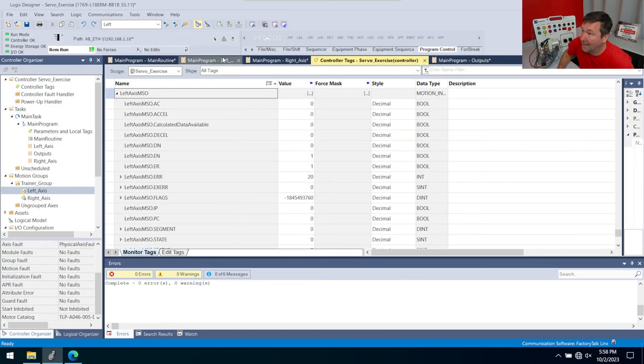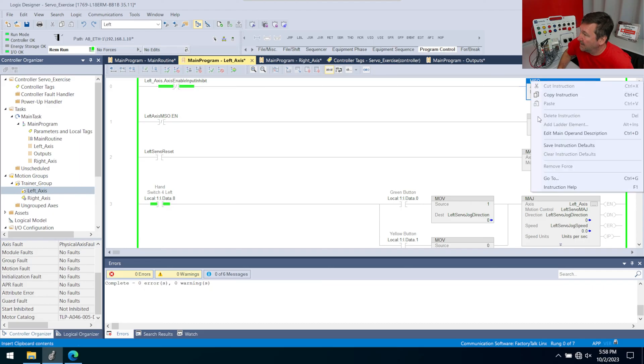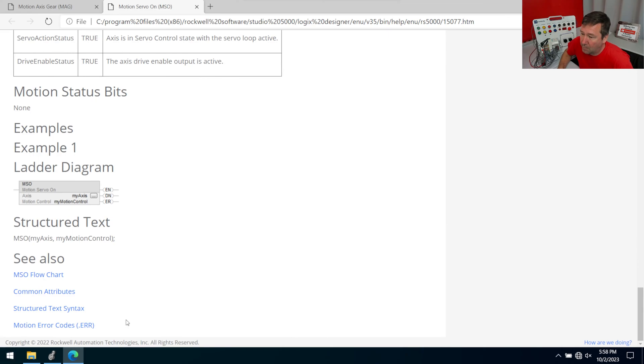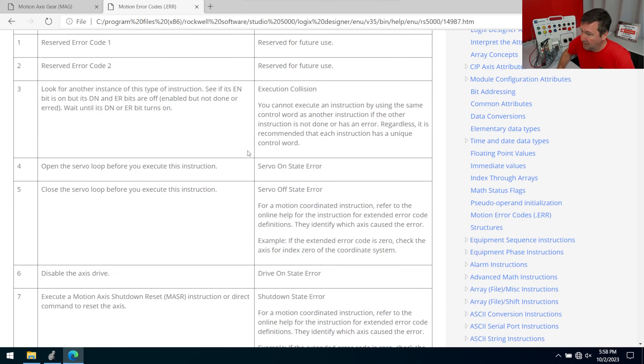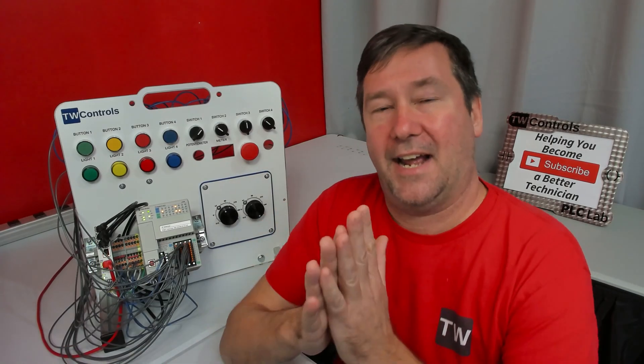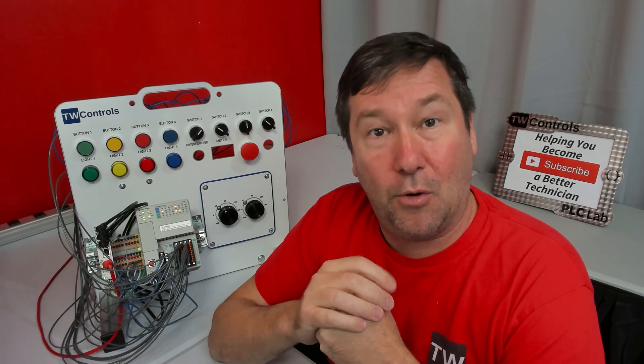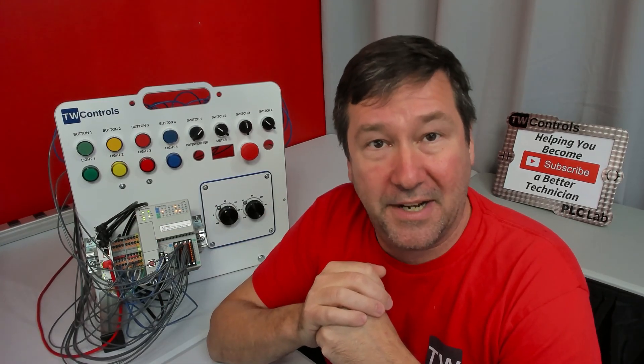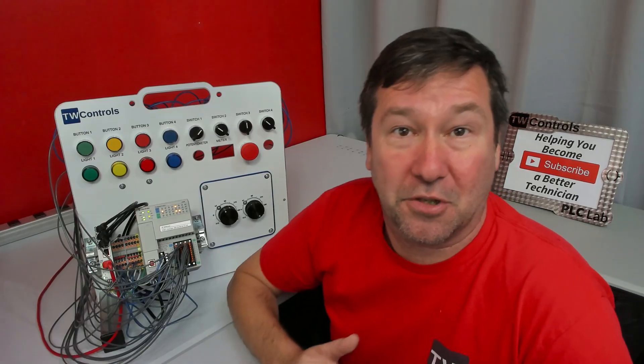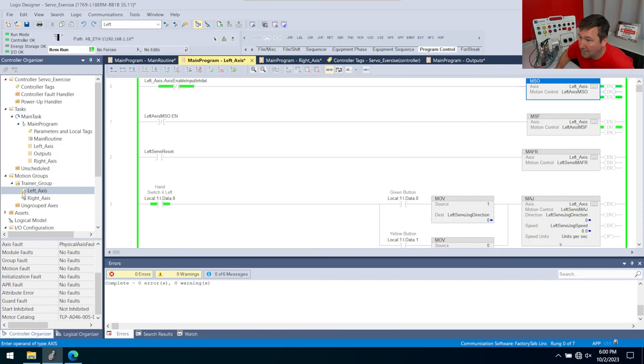To find out what error 20 is, go back to the left axis subroutine, right-click the MSO, go to instruction help, go to the bottom, and find the motion error codes. Error code 20 says the axis is in a faulted state. I know how I faulted the axis — we still had a motion command going on it, we had never issued a stop command, and I turned it. Before we enable this, we need to make sure we're not faulted. Looking for the fault bit, I can see the little yellow triangle, and there it says physical axis fault — that's probably the tag we're looking for.